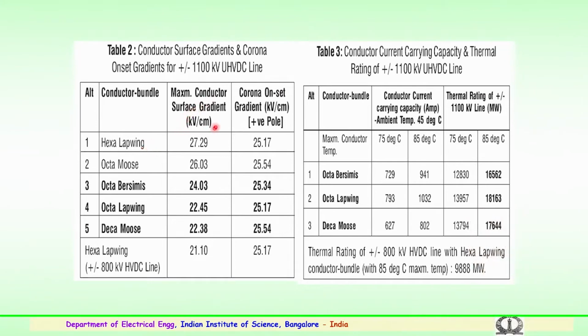You see the maximum conductor surface gradients being 27.29 in corona onset gradient, that is kV per centimeter, 25.17 kV per centimeter for positive pole. Using the Moose conductor with octa, that is an 8 conductor bundle, you get 26.03 kV per centimeter, and going in for 8 conductor Bersimis you get 24, and going for octa, that is 8 conductor lapwing conductors, you get 22.45, and going in for 10 conductor Moose bundle, you get 22.38. These are the estimated values for maximum surface gradient and corona onset gradients for 1100 kV.